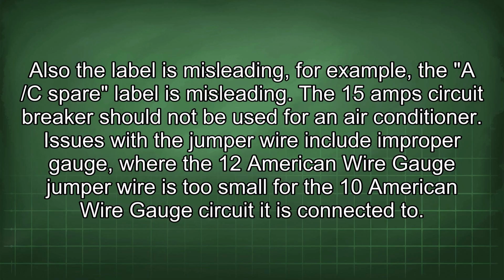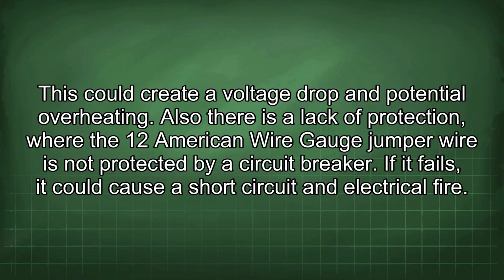Issues with the jumper wire include improper gauge, where the 12 American wire gauge jumper wire is too small for the 10 American wire gauge circuit it is connected to. This could create a voltage drop and potential overheating. Also, there is a lack of protection, where the 12 American wire gauge jumper wire is not protected by a circuit breaker. If it fails, it could cause a short circuit and electrical fire.